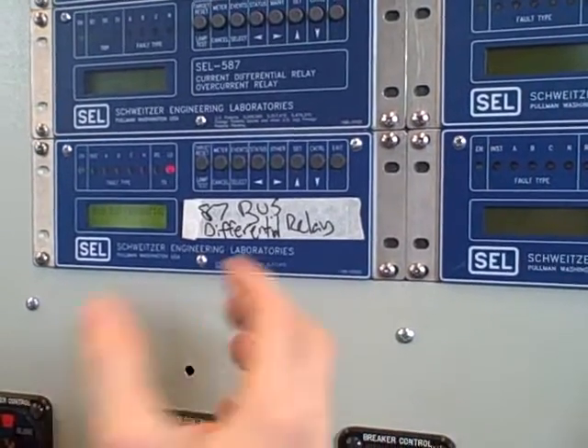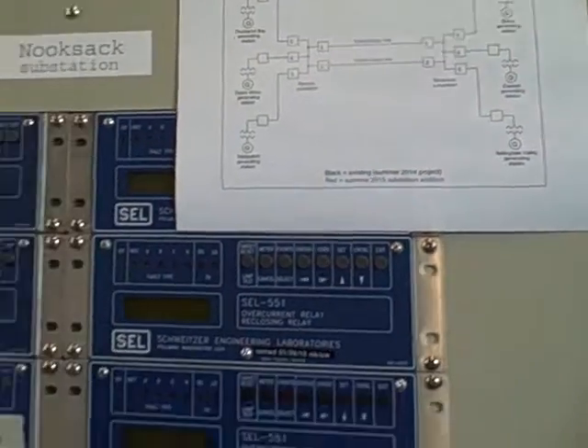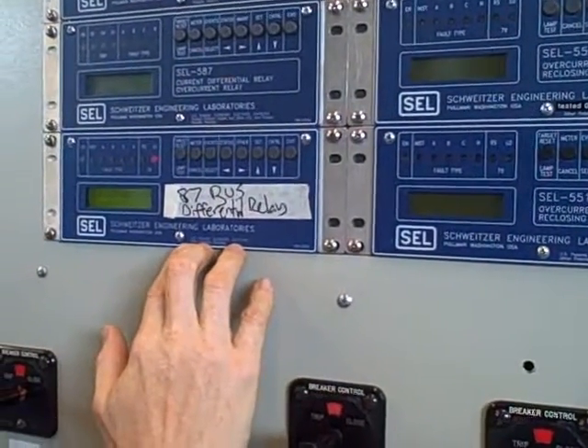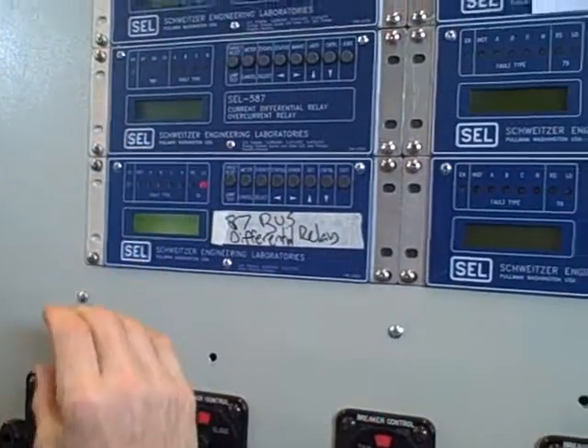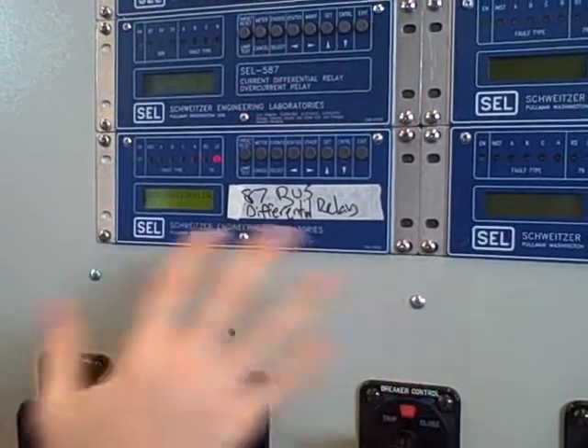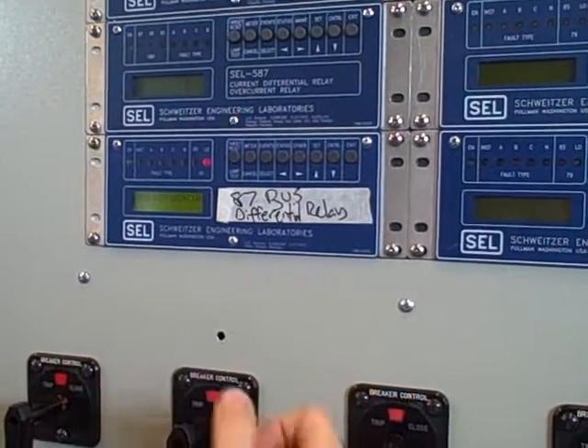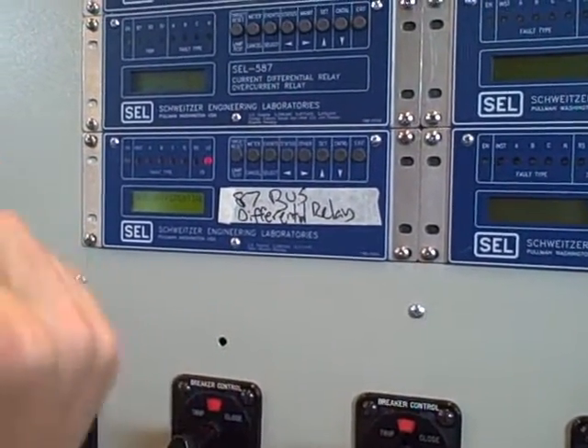We were able to figure out how to hook up the current transformers to give single bus differential protection and we simply use this model 551 as a current sensor. We've got it set up for an instantaneous trip on the lowest pickup value possible, so if it sees any difference of current on the bus — going in versus going out — above its threshold, it trips immediately.